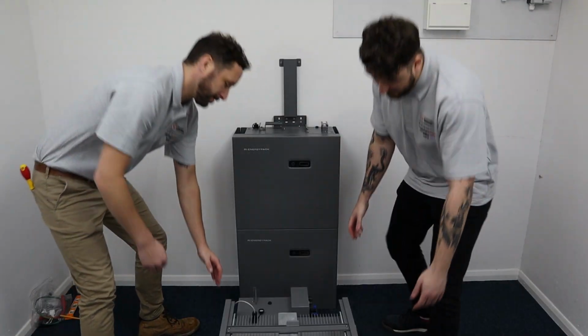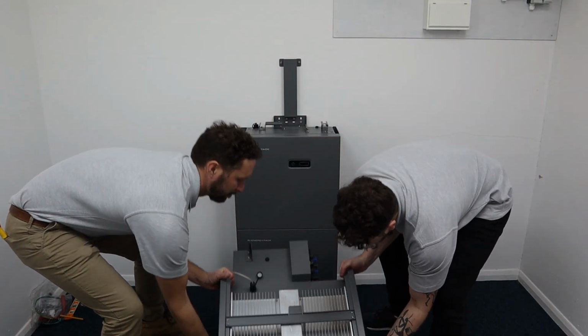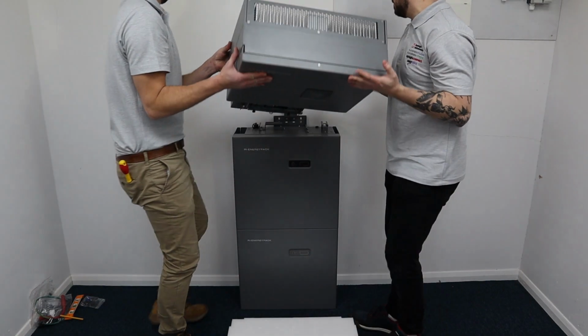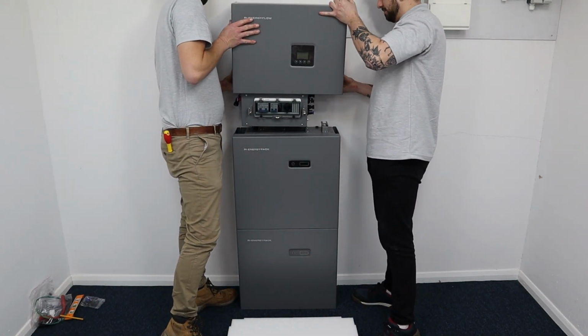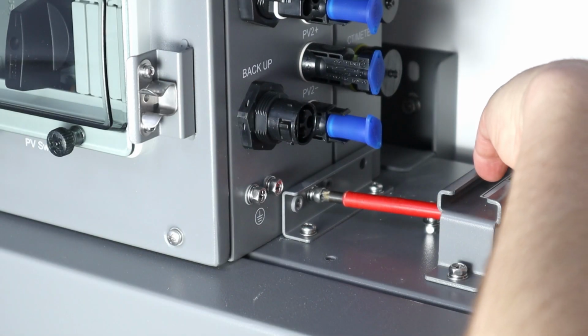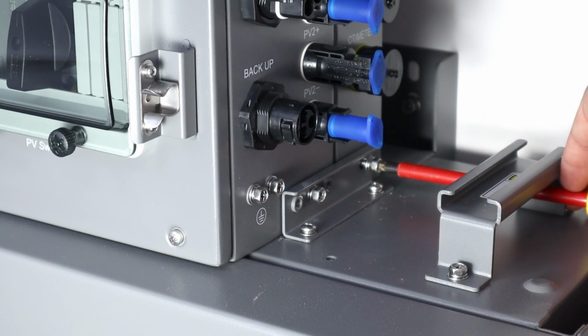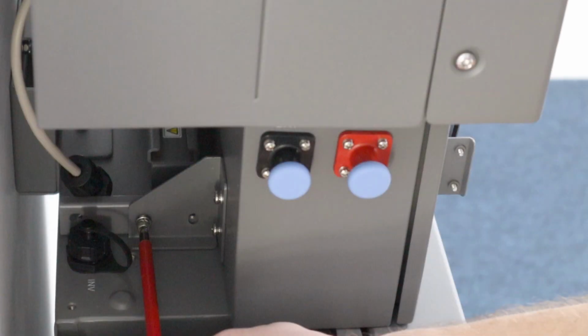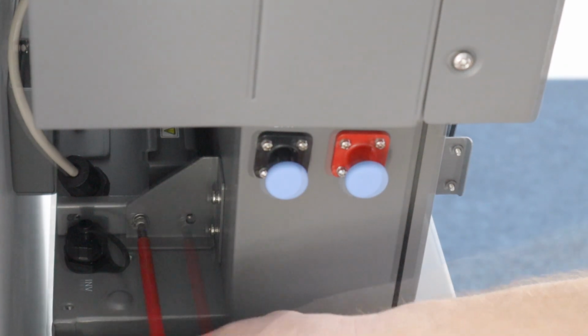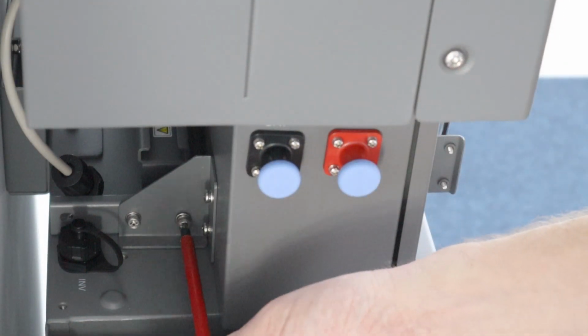Lift the inverter into position on the top battery, making sure that the tab on the back of the inverter engages with the slot on the top of the inverter wall bracket. Next, secure the inverter to the battery housing using the supplied screws. There are 2 screw fixing points on the PV grid side and another 2 on the battery connection side.